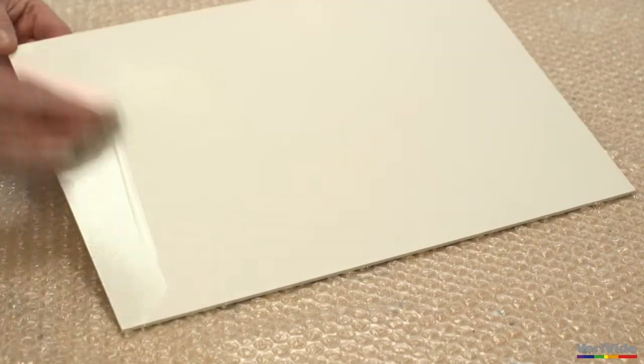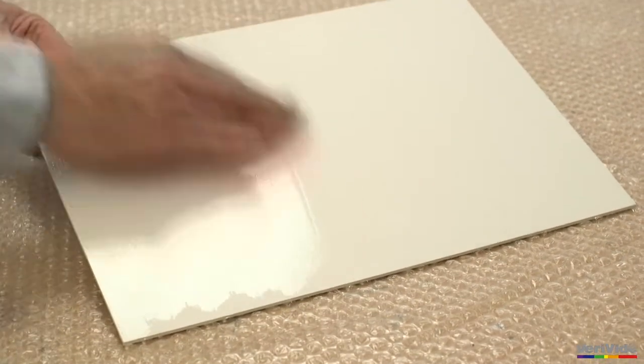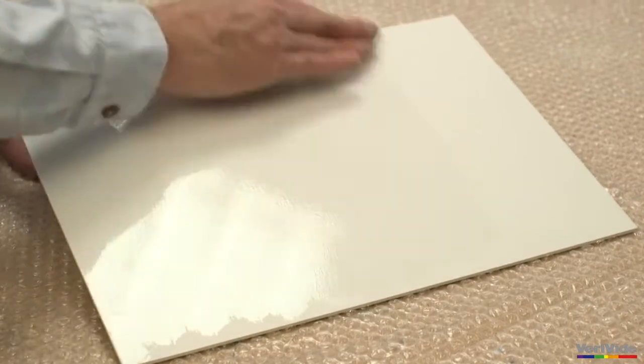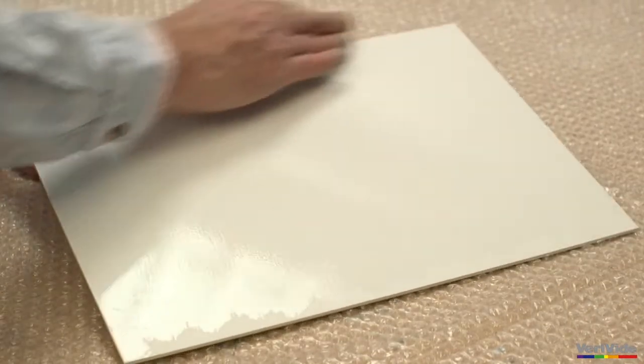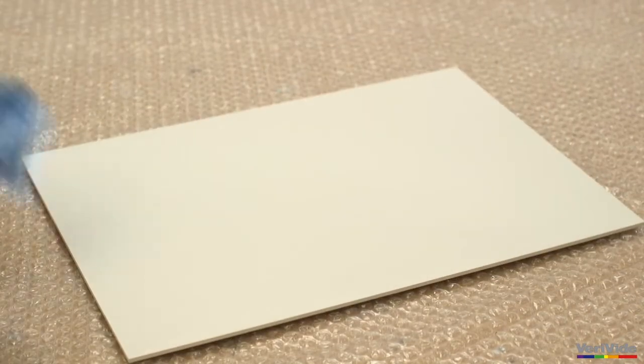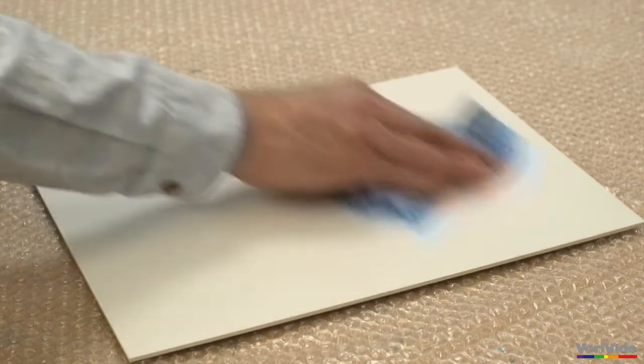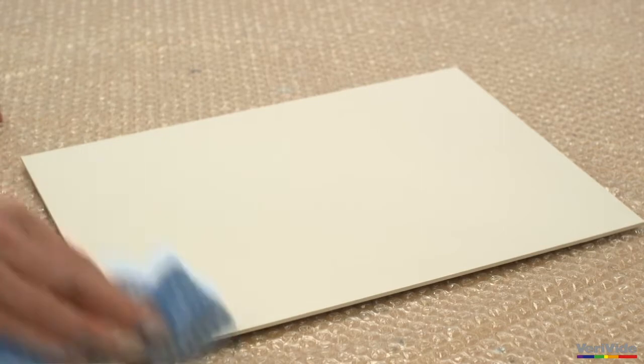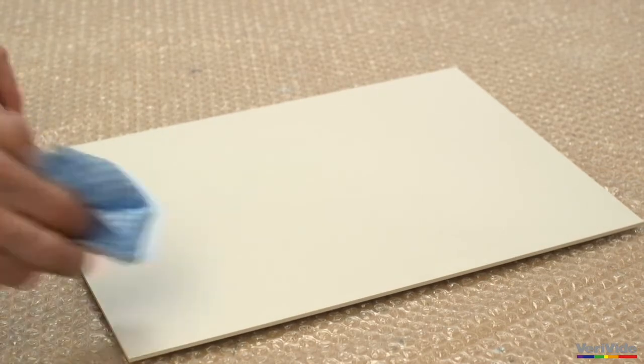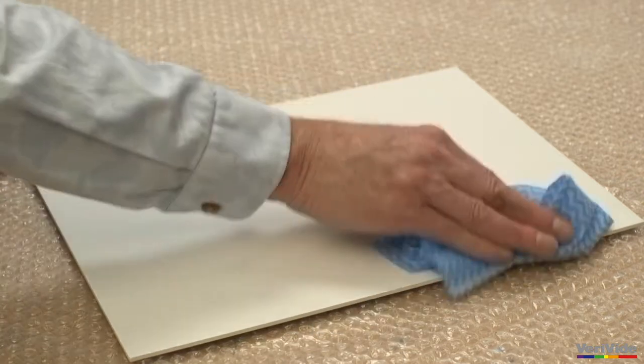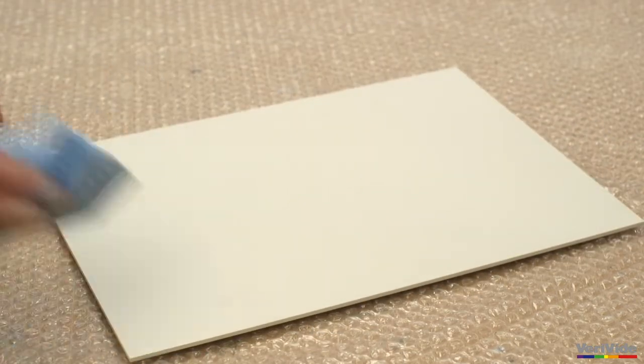In exceptional circumstances, the white uniformity board can be wiped with a damp cloth, using a light detergent if really dirty. It is important that no dirt or scratches are present on the board, otherwise this would result in captured images actually showing patches or inverse scratches. And in this case, you must replace your board with a new one. These can be ordered from Verivide Limited or via our local distributor.